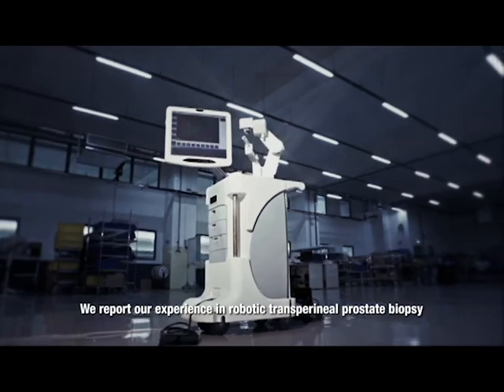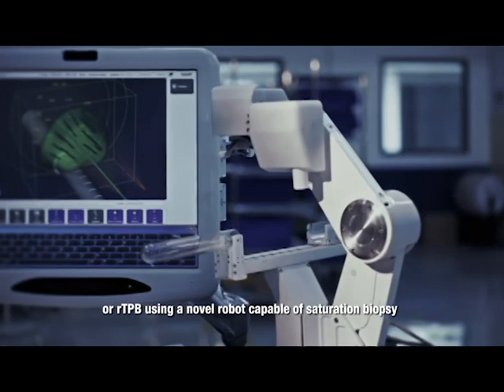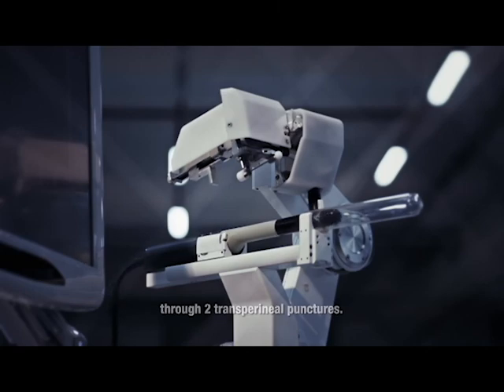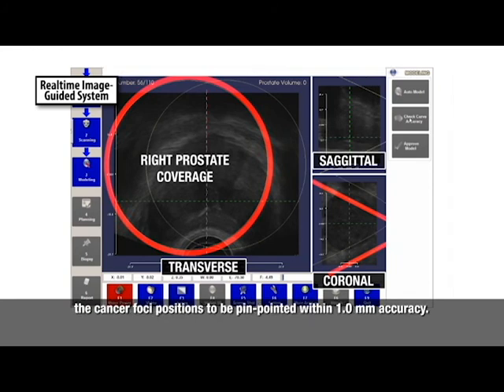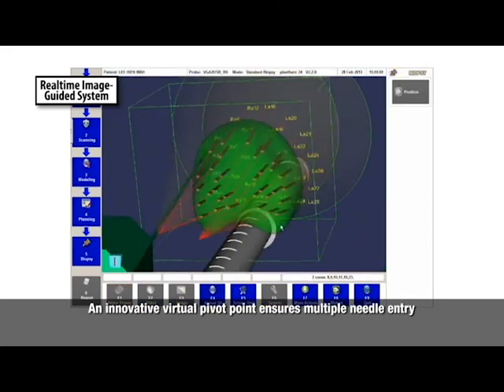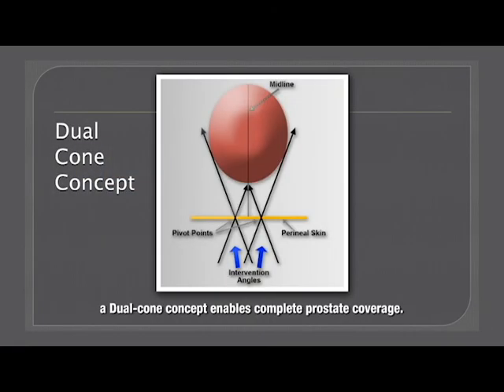We report our experience in Robotic Transperineal Prostate Biopsy, or RTPB, using a novel robot capable of saturation biopsy through 2 transperineal punctures. The intelligent real-time imaging guided system enables cancer foci positions to be pinpointed within 1.0 mm accuracy. An innovative virtual pivot point ensures multiple needle entry through the same point, and a dual cone concept enables complete prostate coverage.